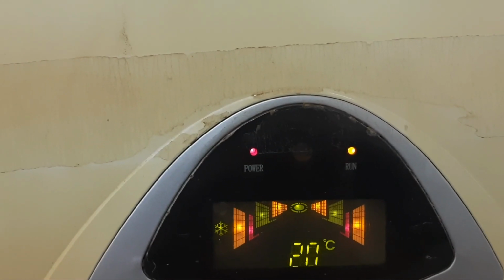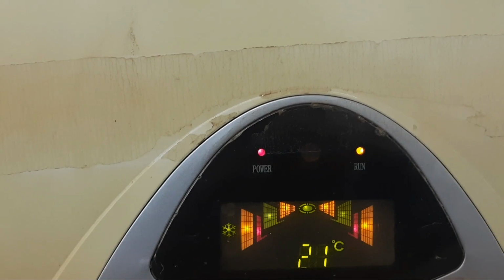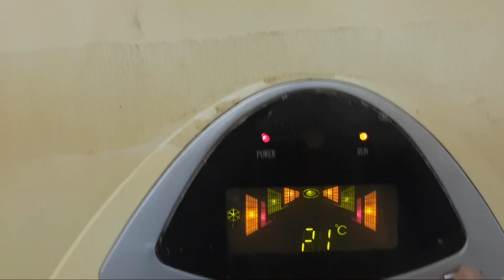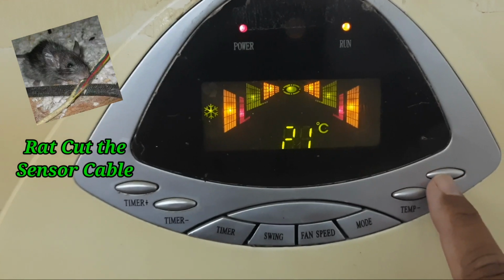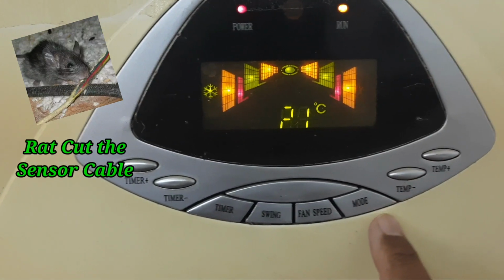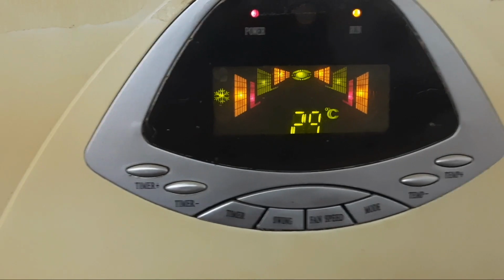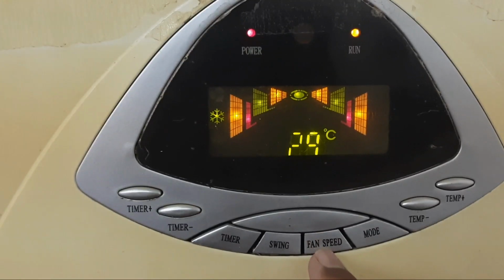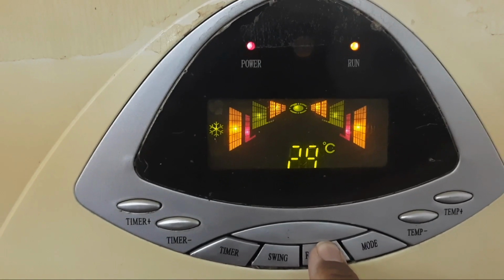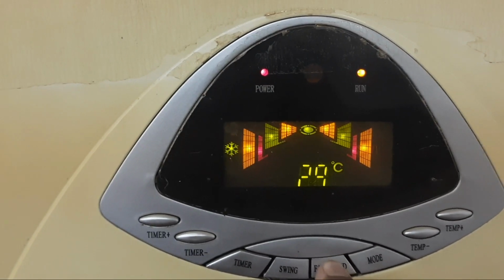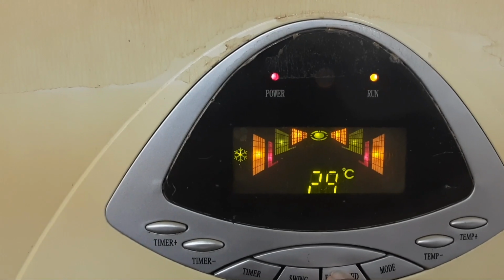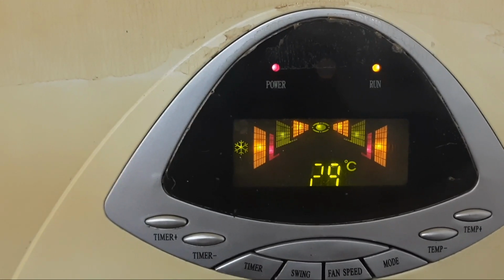When we searched for this issue in the unit, we opened the complete unit and found that the sensor cable was cut. And how was it cut? A rat came inside the unit from somewhere on the drain side and cut the sensor wire of the unit. That's why the error code E2 was coming. When we fixed this error code E2, the unit ran normally after fixing the cable of the sensor.